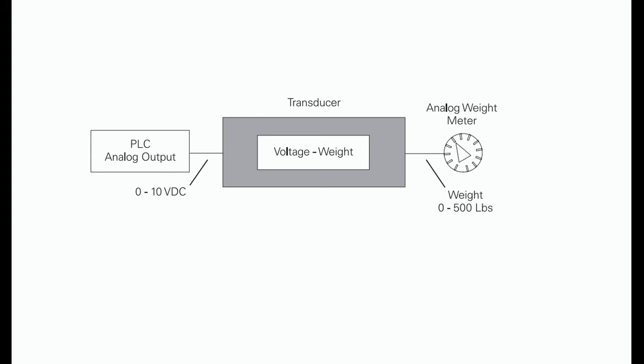Chart recorders, electric motor drives, analog meters, and pressure transducers. Like analog inputs, analog outputs are generally connected to a controlling device through a transducer. The transducer takes the voltage signal and, depending on the requirement, amplifies, reduces, or changes it into another signal which controls the device. In the following example, a 0 to 10 V DC signal controls a 0 to 500 pounds scale analog meter.